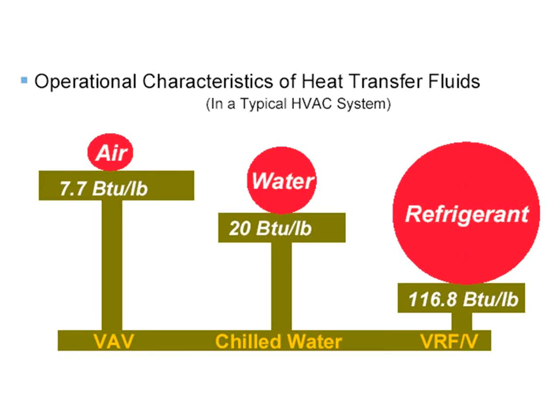If you look at a typical air side system, a VAV zoning system, if you will, air as a heat transfer media can handle about 7 BTUs per every pound of air. A hydronic water system, a chilled water system, can handle 20 BTUs for each pound. A refrigerant-based system, it's 116 BTUs per pound. So we can move a lot more heating and cooling energy around the building in a lot less given space, using a lot less distribution energy. That's really the big benefit here.